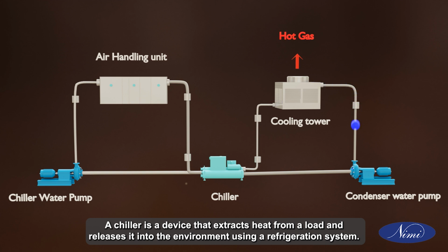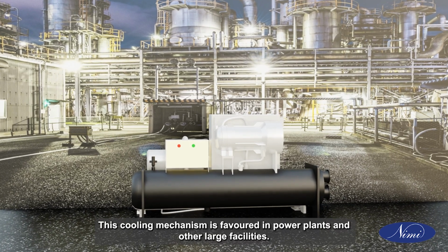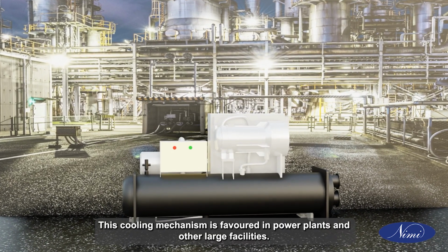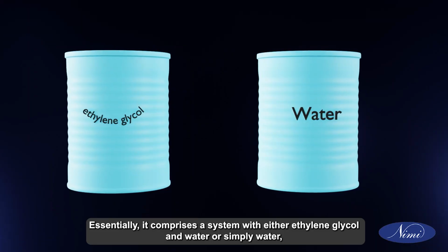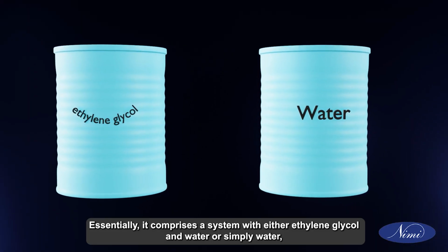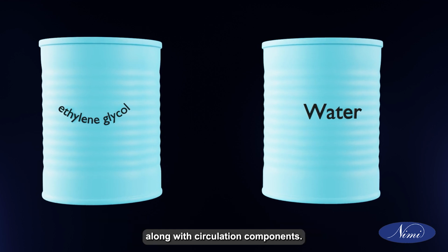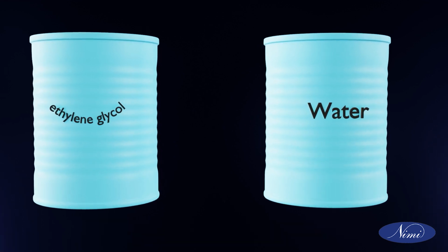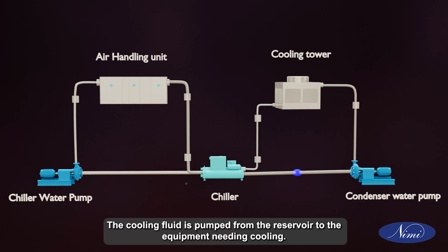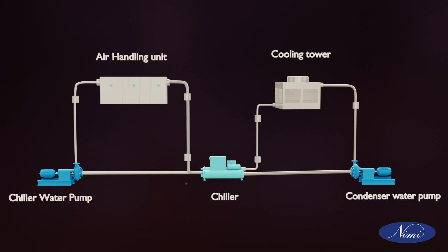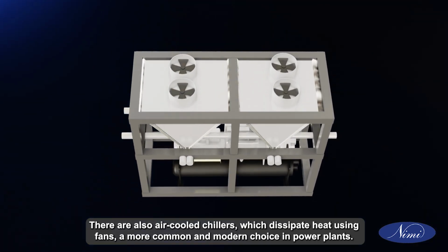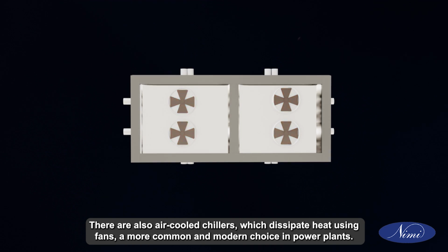What is a chiller? A chiller is a device that extracts heat from a load and releases it into the environment using a refrigeration system. This cooling mechanism is favored in power plants and other large facilities. Essentially, it comprises a system with either ethylene glycol and water or simply water, along with circulation components. The cooling fluid is pumped from the reservoir to the equipment needing cooling. There are also air-cooled chillers, which dissipate heat using fans, a more common and modern choice in power plants.